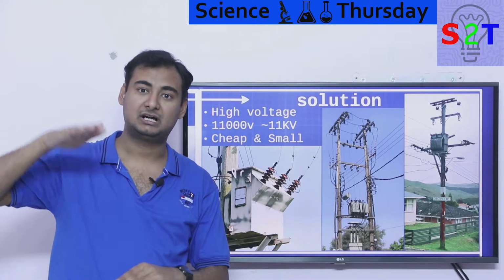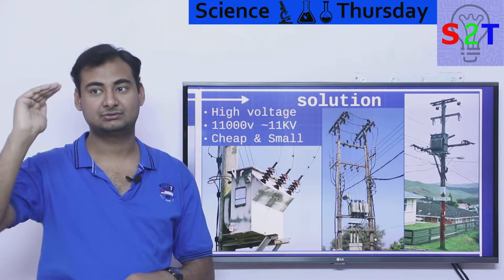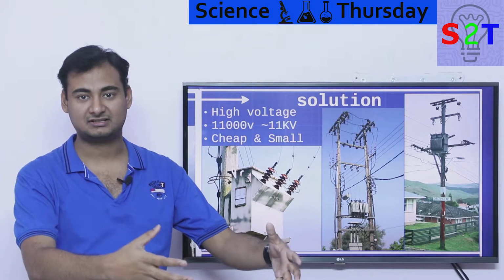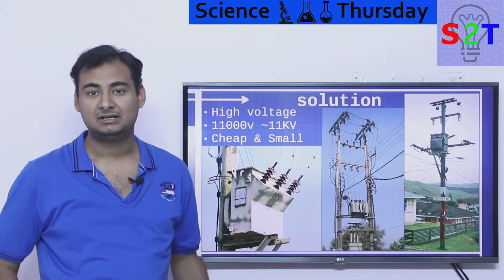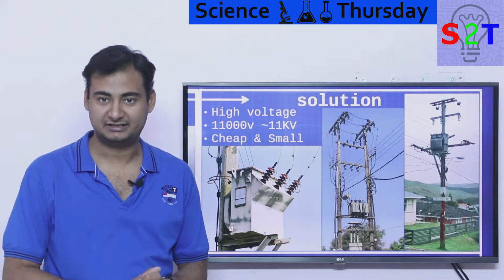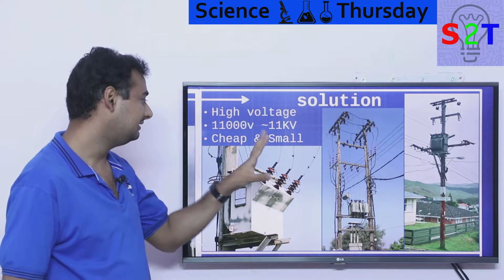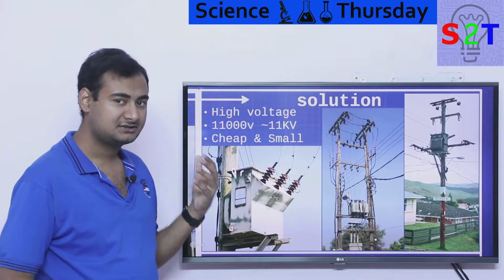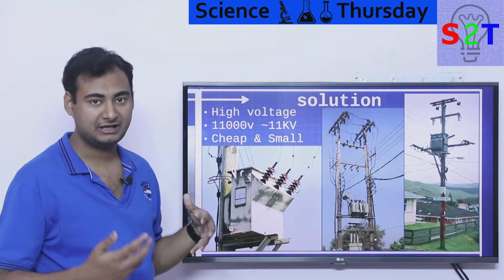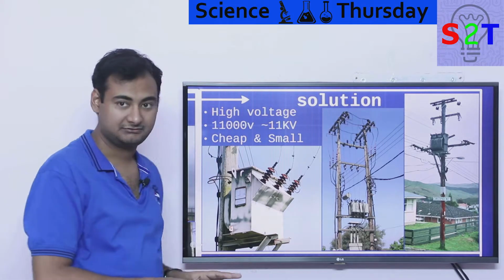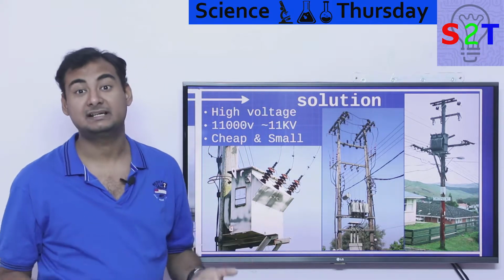It also determines how high you have to keep the lines. You have to make sure that if a giant metal garbage truck goes below a conductor, the electricity does not get excited and jump onto it. So 11 kV has been chosen for that. And there are certain benefits to it. 11 kV is not too high, so the transformers that we need to step down that 11 kV to whatever you need are not that big nor expensive.